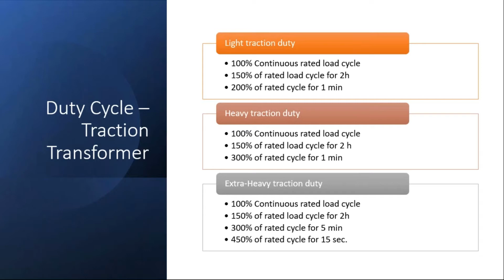So, Bala, this is a very interesting topic here. Traction transformers actually do have a very specific requirement. If you see this 2-hour cycle, it is based on the peak load on these transformers. During transit application, these transformers are very heavily loaded, more than nameplate rating, in the morning 2 hours and evening 2 hours. That's the reason they're defined, and based on the transit load, they are classified as light duty, heavy duty, or extra heavy duty.